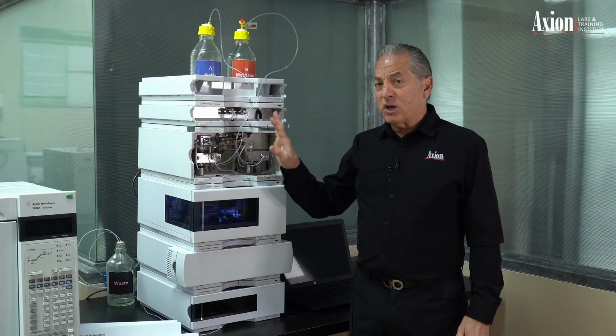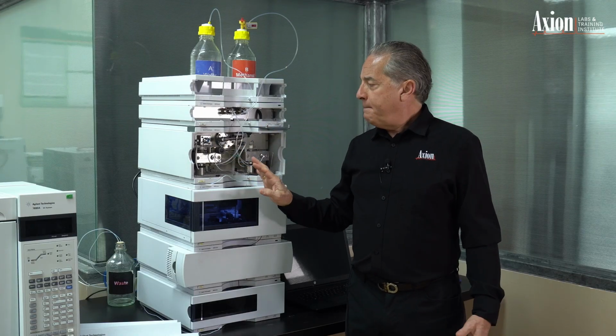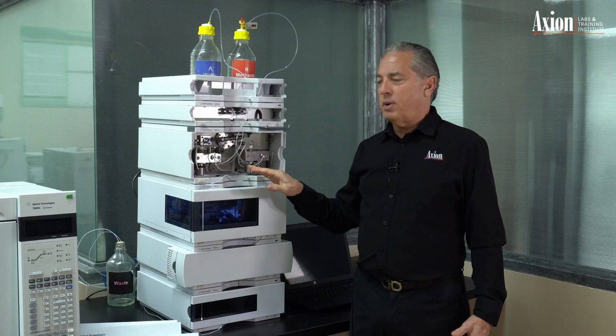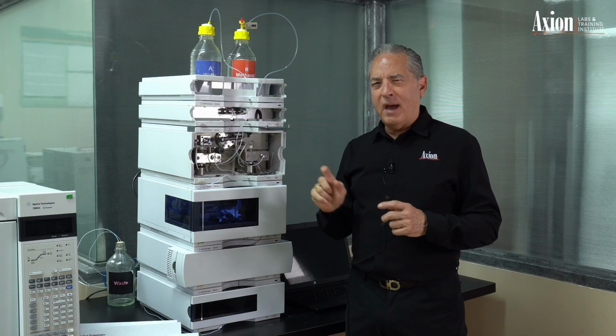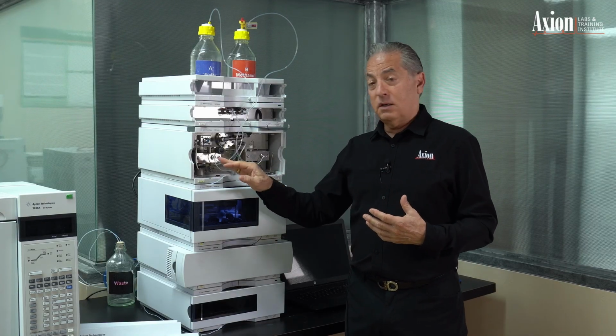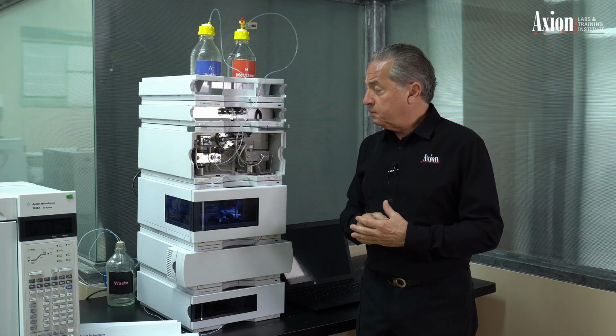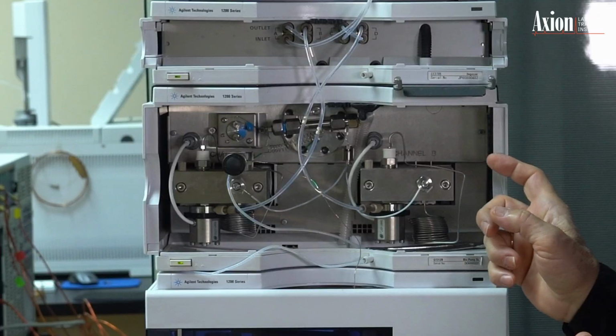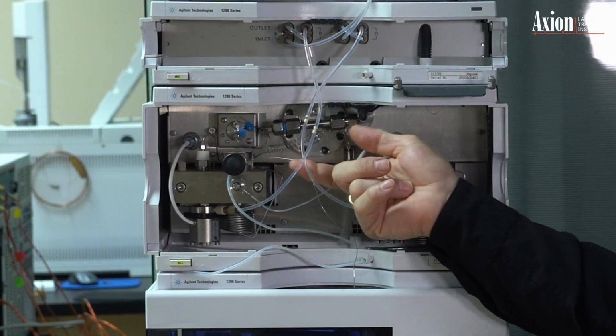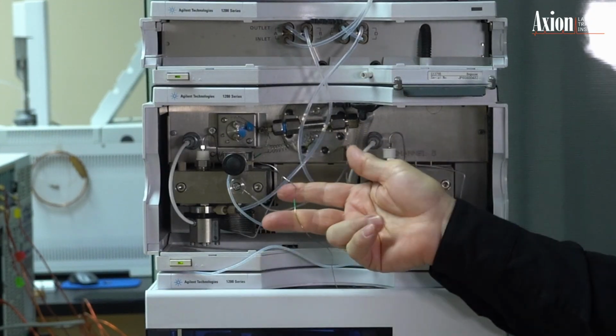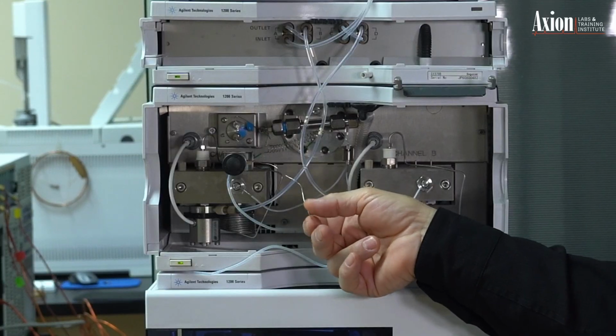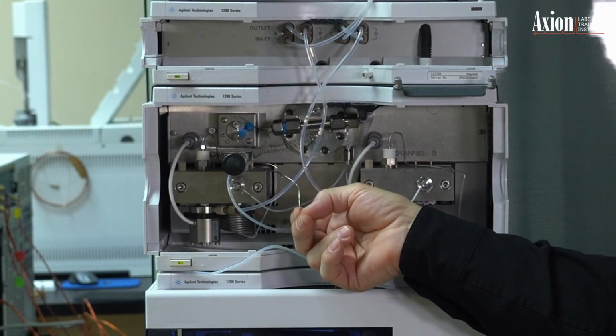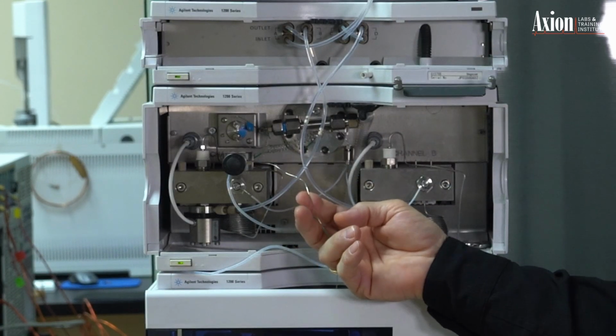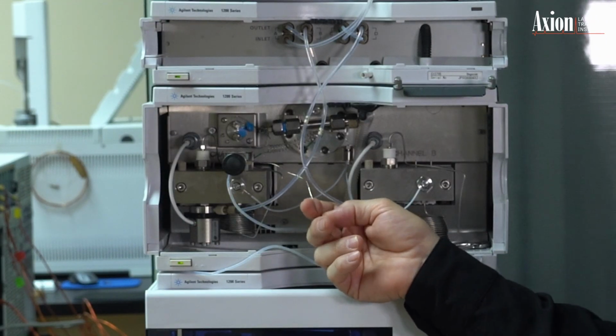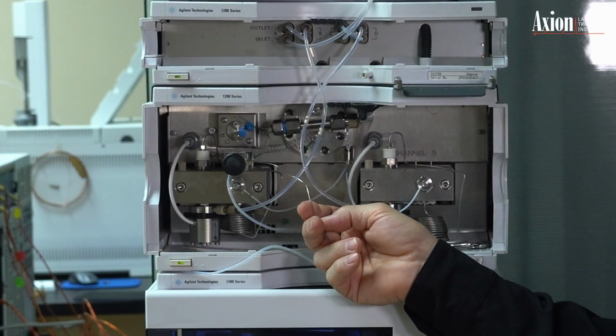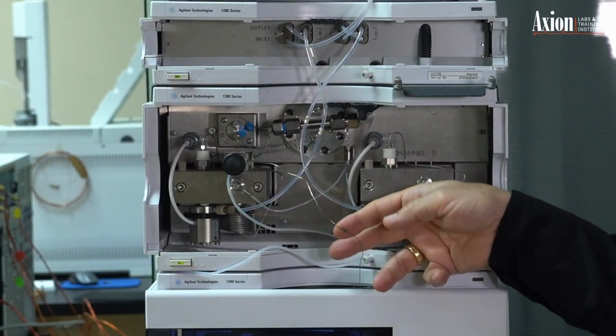This design is more expensive than what's called the quaternary pump because we have 2 high pressure pumps. These are the expensive parts of the instrument. You can imagine the machining that goes on to make these things so reproducible. Okay, so now we have mobile phase coming out of the pump, and this is the high pressure line coming out. Again, it's capillary tubing. Axion likes to use the really small outer diameter tubing, but this is running high pressure. This instrument will go up to 9,000 psi, so this tubing will hold that kind of pressure.